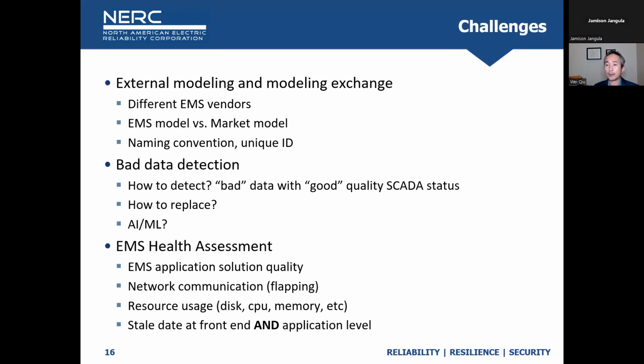You may model the zero impedance, called ZBR, or someone else may model ZBR as a breaker. Because it's different, this causes some algorithms to behave differently: if you model as a breaker versus as a zero ZBR, it can impact the Jacobian due to zero entries on the diagonals. So they see a lot of problems here.